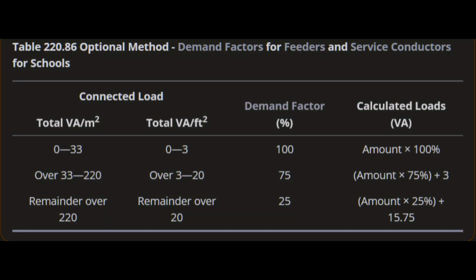Imagine you run a standard calculation, very conservative, and it says you need, I don't know, a 3,500 kVA service transformer and main gear. Huge, expensive. But then you apply this optional school method with its demand factors. Maybe it calculates out to only needing a 2,500 kVA service. That's a massive difference. Huge. You're not just saving on the cost of copper wire. You're potentially downsizing the main transformer, the switchgear, the concrete pad it sits on, the room it occupies. The footprint, the cost, the installation time. All of it. It reduces complexity and cost significantly, all while being fully compliant with the safety standards laid out in Chapter 2. It's pretty amazing, really, that such substantial savings can hinge on a few percentages in a table based on square footage. It really is.